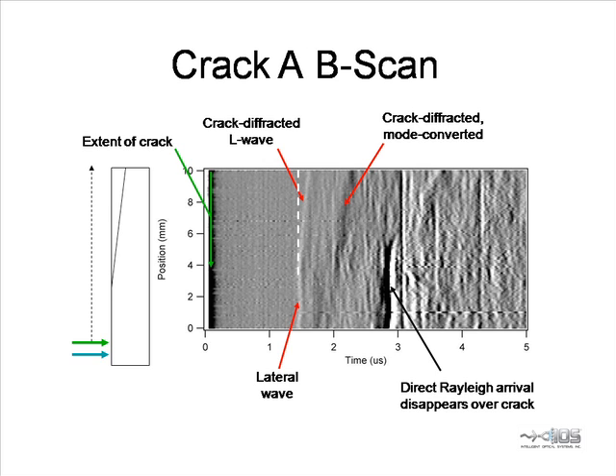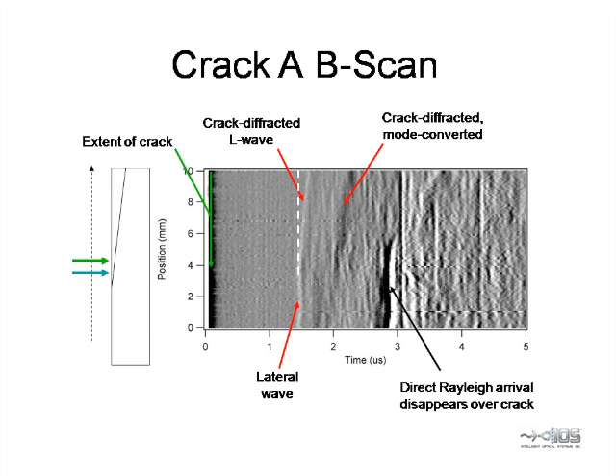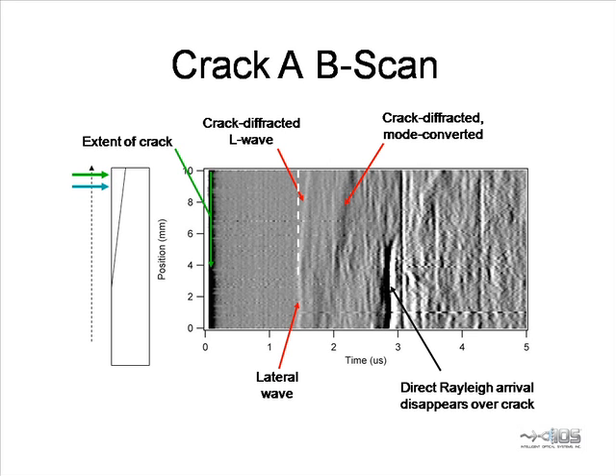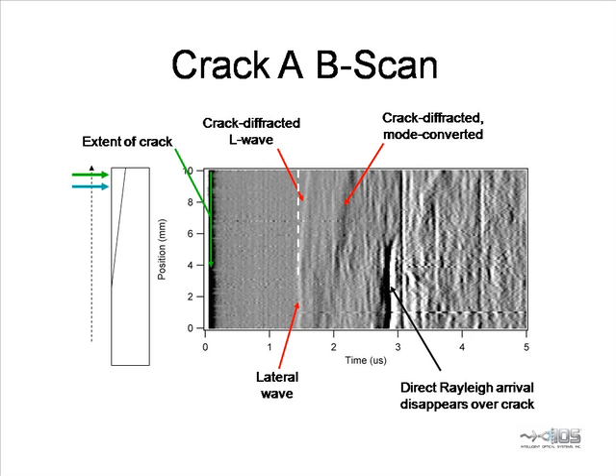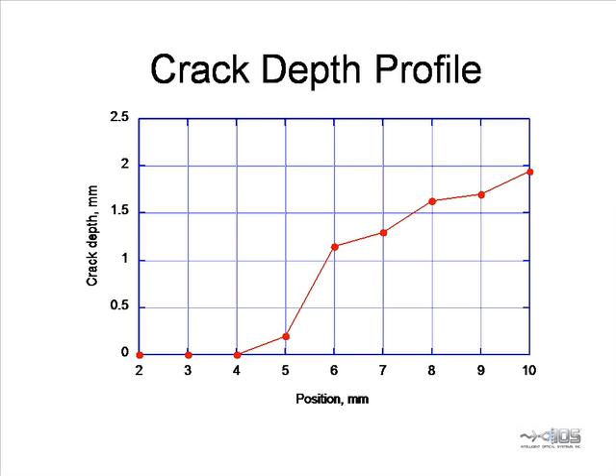This is a B-scan of the crack shown in the previous video. The crack starts at 4 millimeters and deepens at larger scan positions. The beams are scanned together along the crack. Note that the direct Rayleigh wave arrival disappears as the crack opens. The crack manifests itself as an increasing time delay of the lateral wave, and we also observe a mode-converted arrival. Using the B-scan data and the measurement scheme described earlier, we have plotted the crack depth versus position. The crack deepens along the scan and reaches a depth of 2 millimeters at the end of the scan.